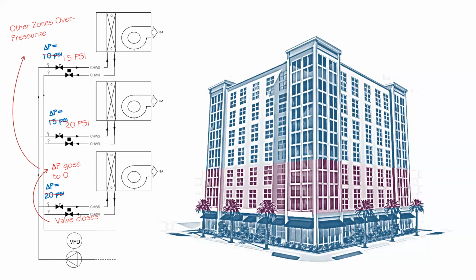The extra pressure in the system is then distributed over to the other zones and they become overpressurized. The valves will overflow and cause too much heat transfer, and the discharge air temperature could be disrupted. Then the command will be sent to modulate the valve more closed, and all of this commotion happens with no changes in load to the space. And then, just in case that wasn't a big enough mess, the same time overpressurization of the far zone will cause the VFD to ramp down, which will then likely cause an underflow that'll need to be corrected. Eventually, the system will find a steady state, but it will see an anomaly in that time, or a mess.